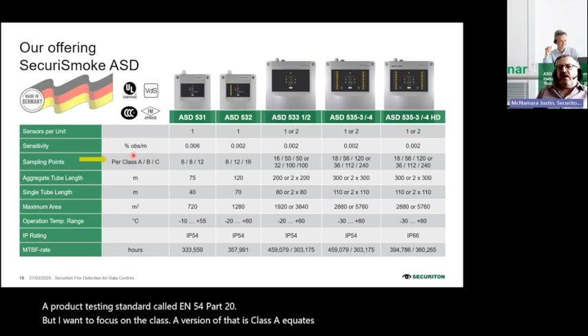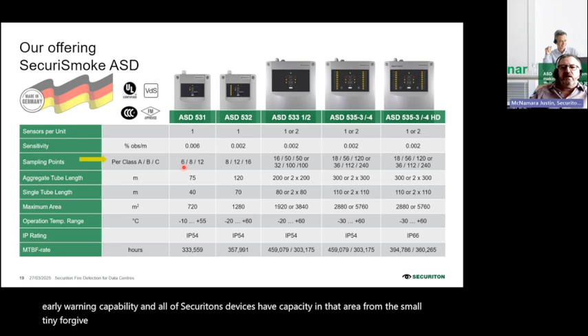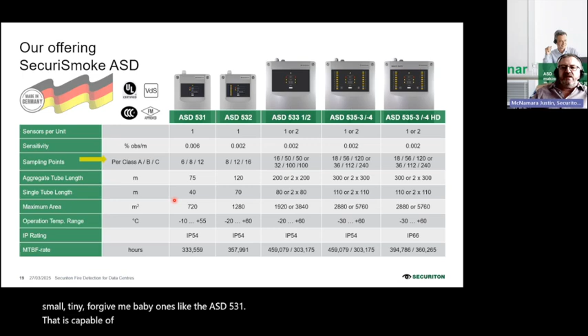Class A equates to high sensitivity, very early warning capability, and all of Securiton's devices have capacity in that area, from the small, tiny ones like the ASD 531, capable of having 6 Class A holes, all the way up to the much bigger devices, the ASD 535, where we can handle up to 36 Class A holes, and anywhere in between.